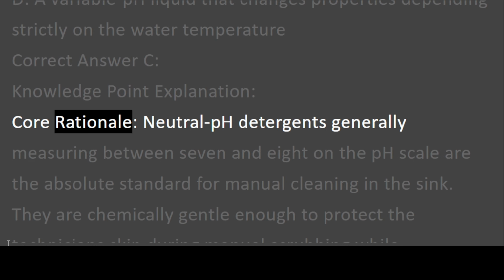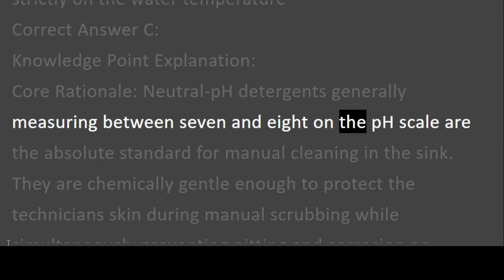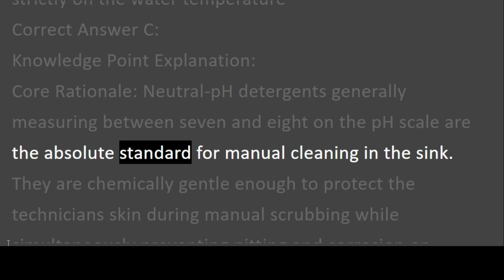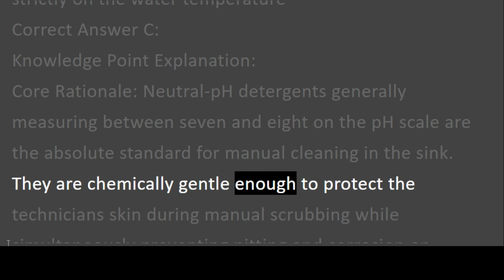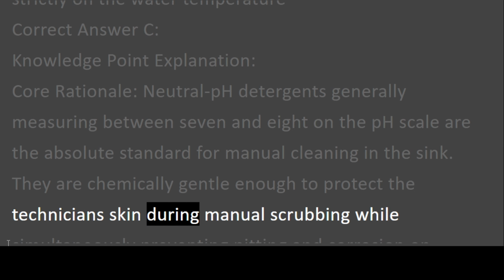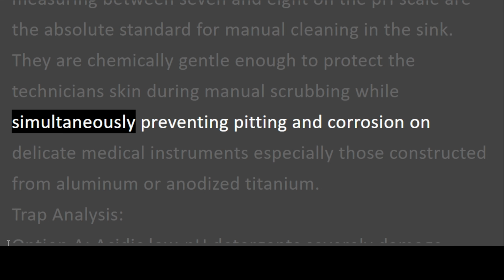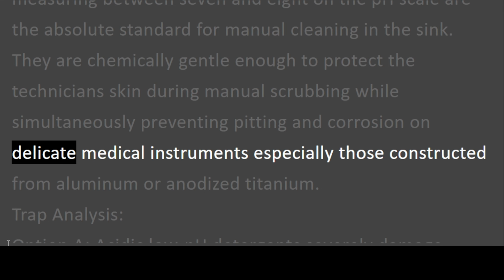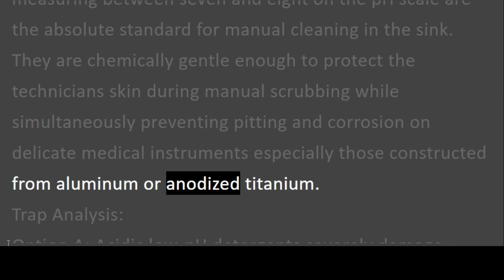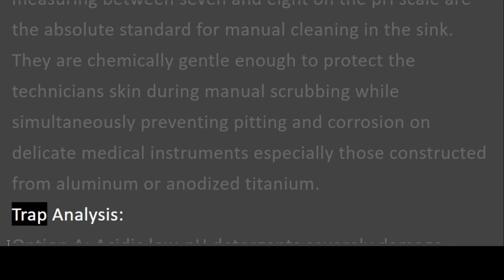Core rationale. Neutral pH detergents, generally measuring between 7 and 8 on the pH scale, are the absolute standard for manual cleaning in the sink. They are chemically gentle enough to protect the technician's skin during manual scrubbing while simultaneously preventing pitting and corrosion on delicate medical instruments, especially those constructed from aluminum or anodized titanium. Trap analysis.